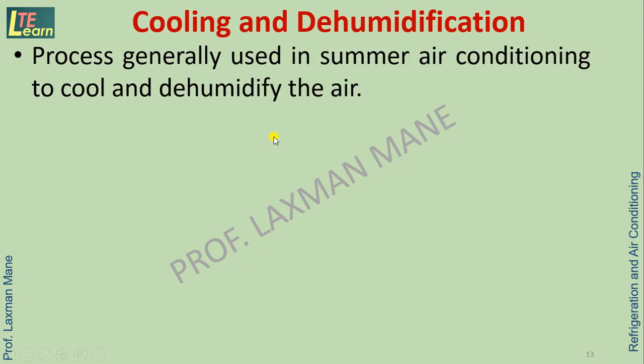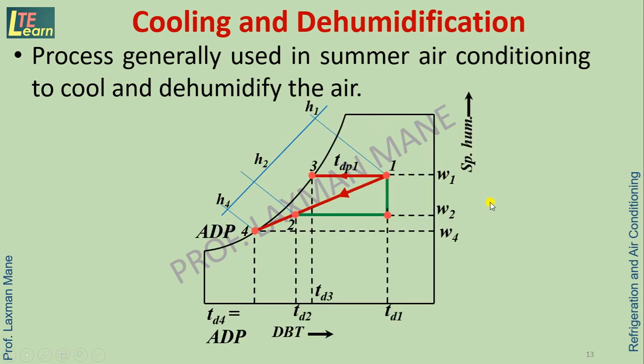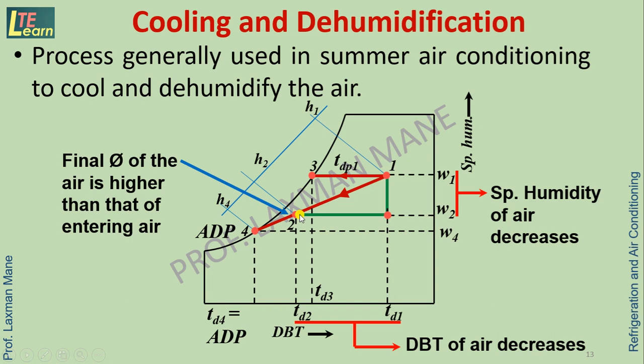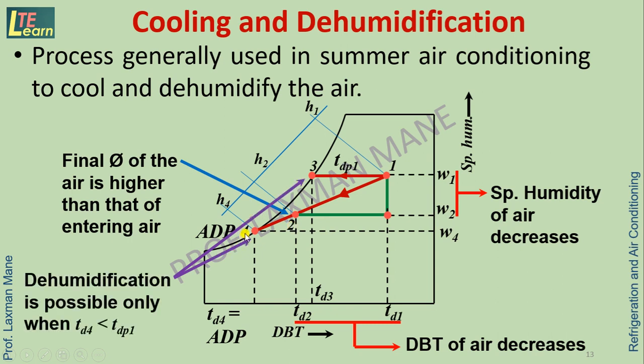Cooling and dehumidification is a process generally used in summer air conditioning to cool and dehumidify the air. The process is shown as line 1 to 2 on the psychrometric chart, where Td4 is the coil temperature. Dry bulb temperature decreases from Td1 to Td2, and specific humidity decreases from W1 to W2. The final relative humidity of the air is higher than that of the entering air. Dehumidification is possible only when Td4 (coil temperature) is less than Tdp1 (dew point temperature of entering air).